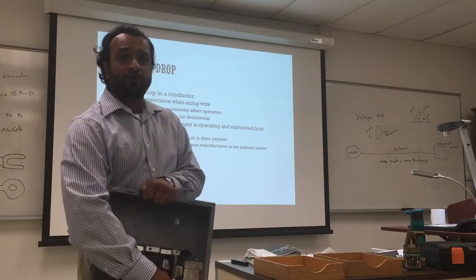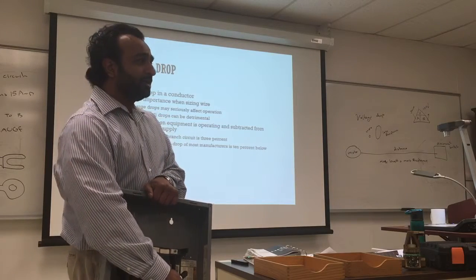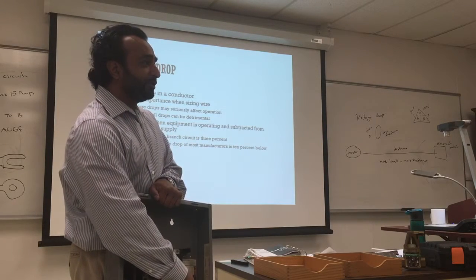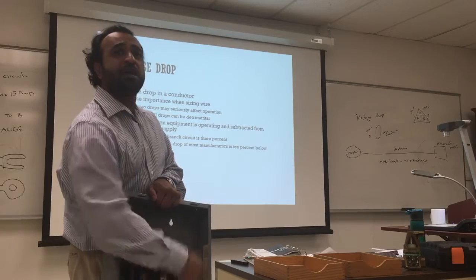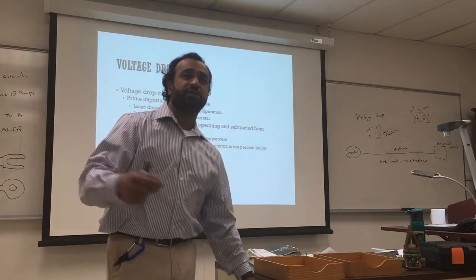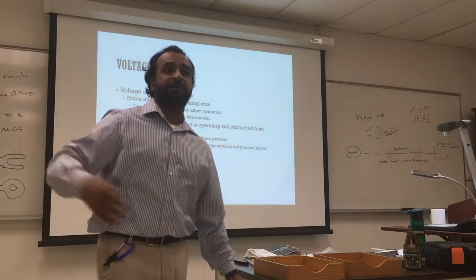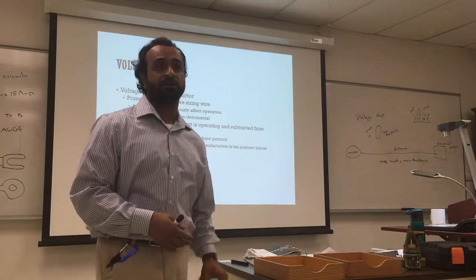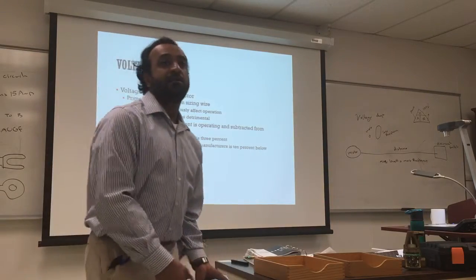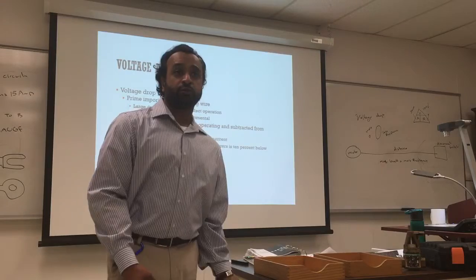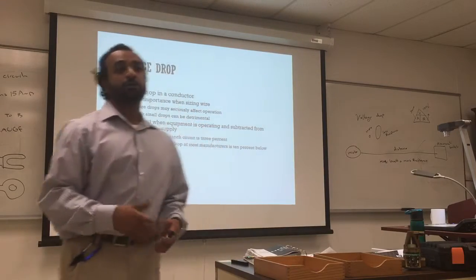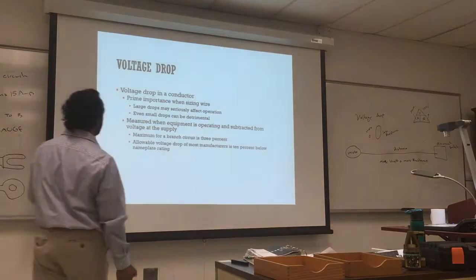Same thing you have in a connection. Those connections after a while will rust, they don't connect as well. The connection between the wires will rust and have some accumulation on it, so probably you will lose drops of voltage here and there. The 5% became 10%, and suddenly the equipment is not running correctly. The motor is not going to run as well as it used to, so probably it's drawing more now. That could be another issue.